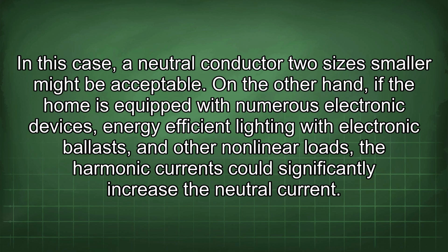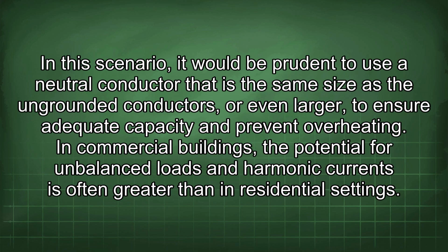On the other hand, if the home is equipped with numerous electronic devices, energy-efficient lighting with electronic ballasts, and other nonlinear loads, the harmonic currents could significantly increase the neutral current. In this scenario, it would be prudent to use a neutral conductor that is the same size as the ungrounded conductors, or even larger, to ensure adequate capacity and prevent overheating.